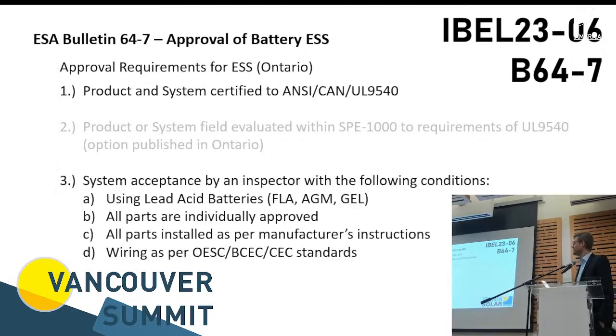The field evaluation, I put that in gray because that's something I would not necessarily recommend, because it's just a lot more difficult. The other option is you can still do lead-acid batteries under both the directives of Bulletin 64.7 or the BC Bulletin, even though lead-acid batteries do not, at the moment at least, have an equivalent testing method to UL 9540A as lithium batteries have. UL is working on a test standard that can also test chemistries that are not lithium, but until that is out, the deviation option and the variance request can be done, so that you can use a standard old-fashioned lead-acid battery like a flooded lead acid or AGM or whatever system it is.